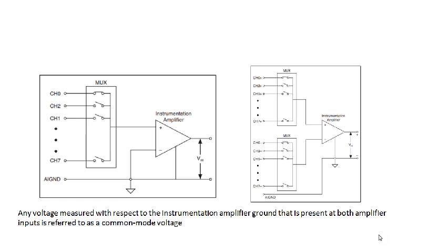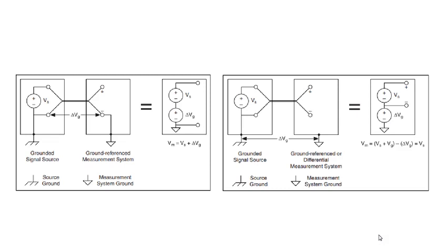The advantage of differential signal measurement is its high common mode rejection ratio. This is because signals common to both wires are cancelled out by the differential amplifier. In a single-ended system, since the measurement system and signal source grounds are not at the same potential, the difference in voltages is also measured, giving erroneous values and affecting accuracy.